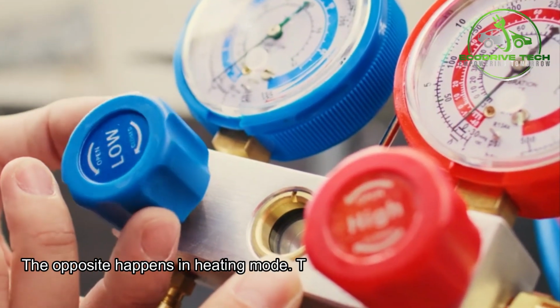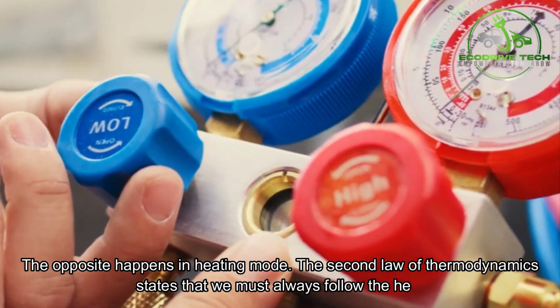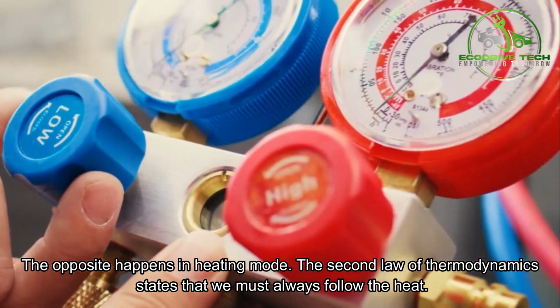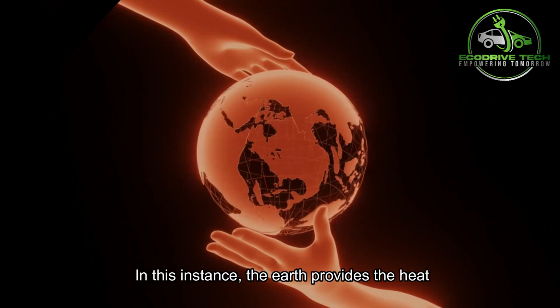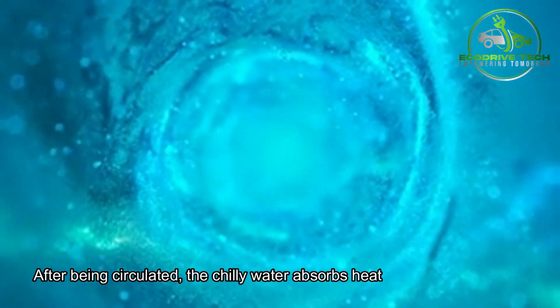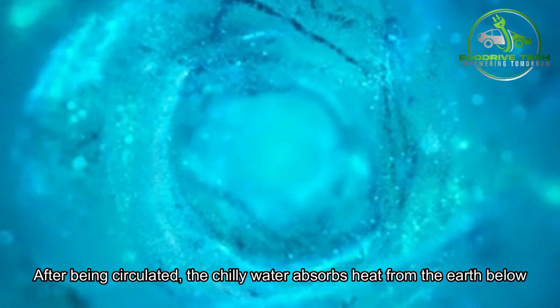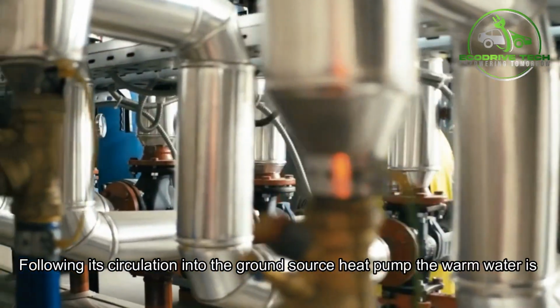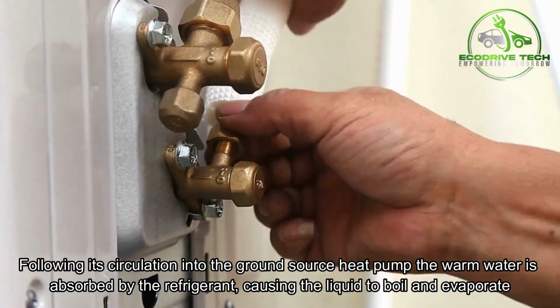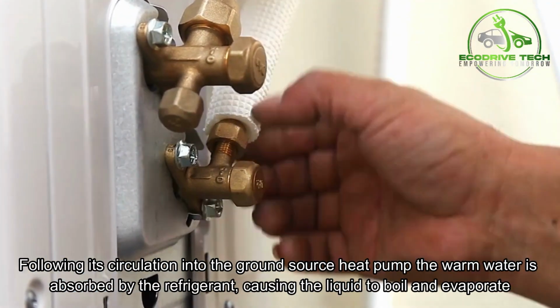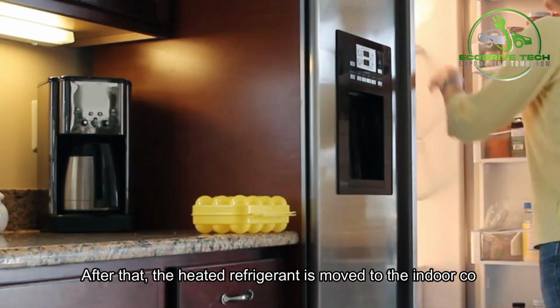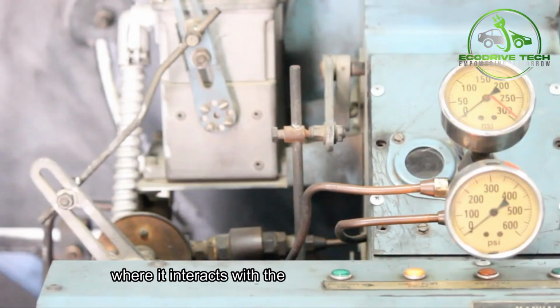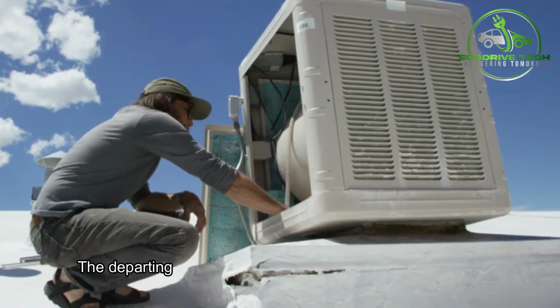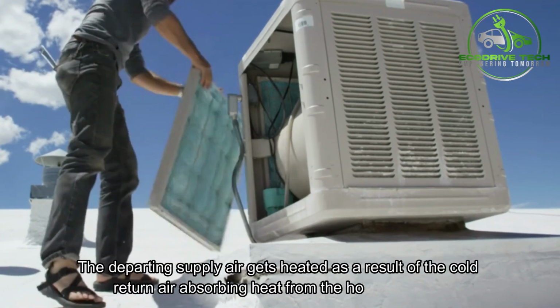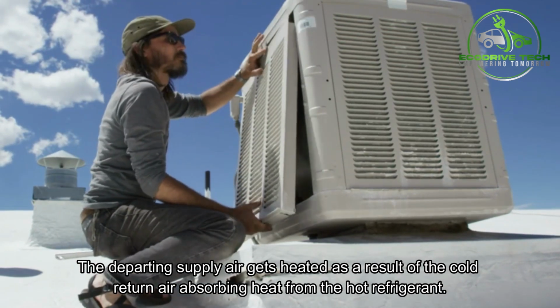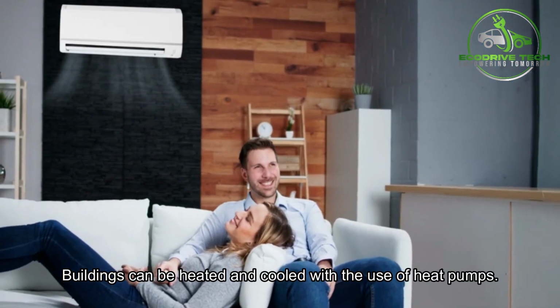The opposite happens in heating mode. The second law of thermodynamics states that we must always follow the heat. In this instance, the Earth provides the heat. After being circulated, the chilly water absorbs heat from the Earth below. Following its circulation into the ground source heat pump, the warm water is absorbed by the refrigerant, causing the liquid to boil and evaporate. After that, the heated refrigerant is moved to the indoor coil, where it interacts with the space's colder return air. The departing supply air gets heated as a result of the cold return air absorbing heat from the hot refrigerant. Buildings can be heated and cooled with the use of heat pumps.